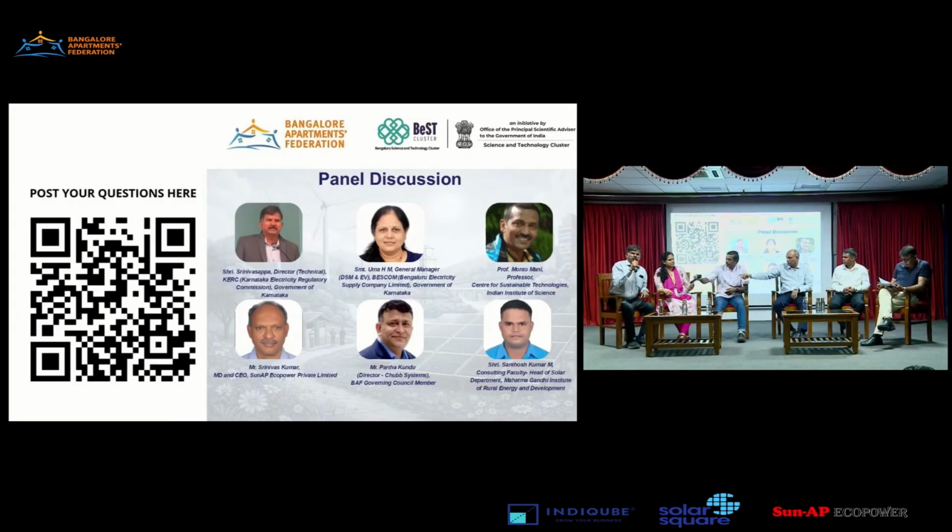Correct. Whenever you enhance the transformer, that means replacing the existing lower capacity transformer with a higher capacity transformer, then also you require the permission of the Chief Electrical Inspector, because he has to come and see whether all the safety guidelines and regulations have been complied with. So therefore, before that, you cannot charge that transformer.